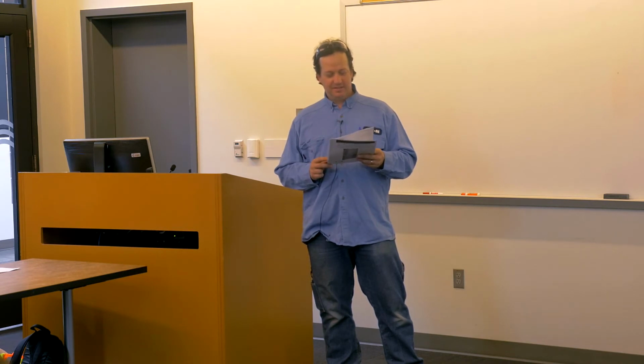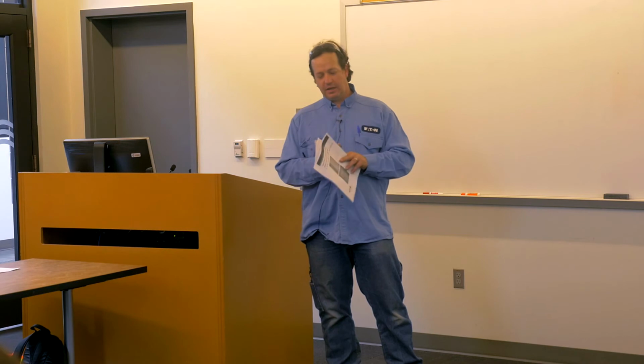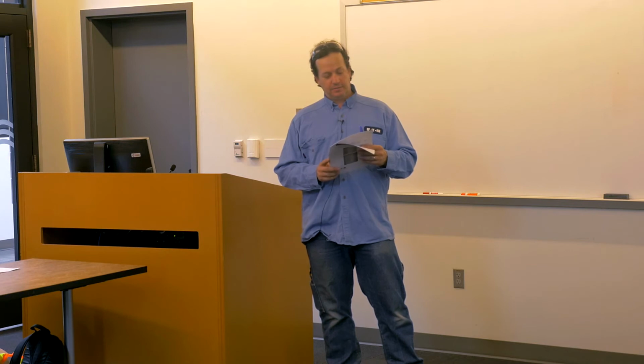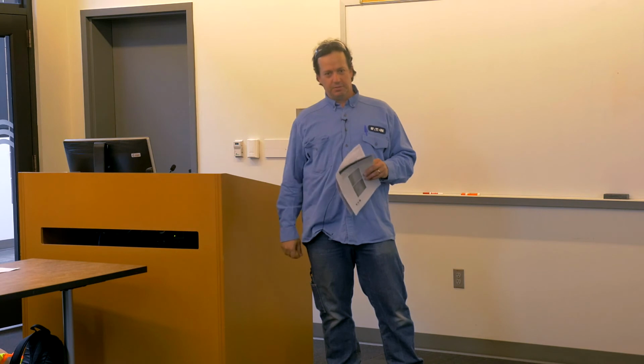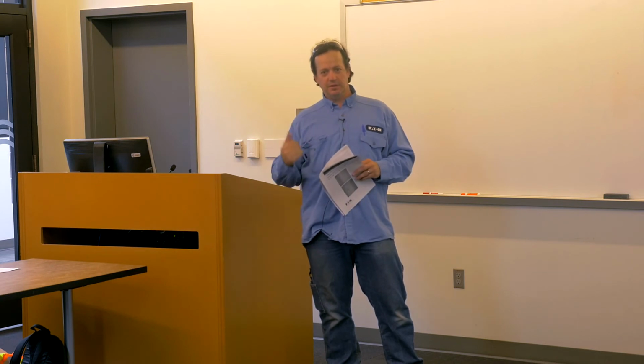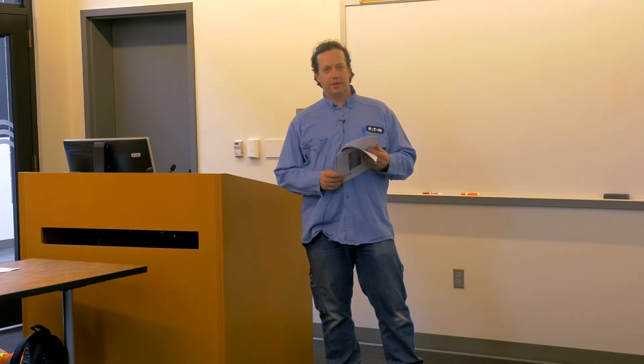On these medium voltage switches, they all have arcing blades, and that's one thing on your rounds you could check - do a visual inspection, make sure they're set in there snug. It's just a good thing to look at periodically. These all have inspection windows.